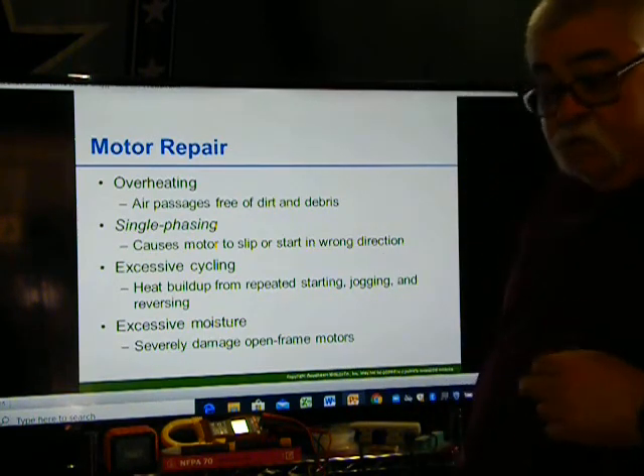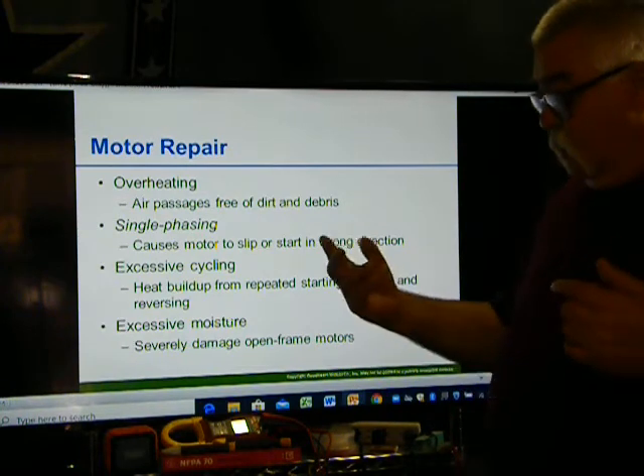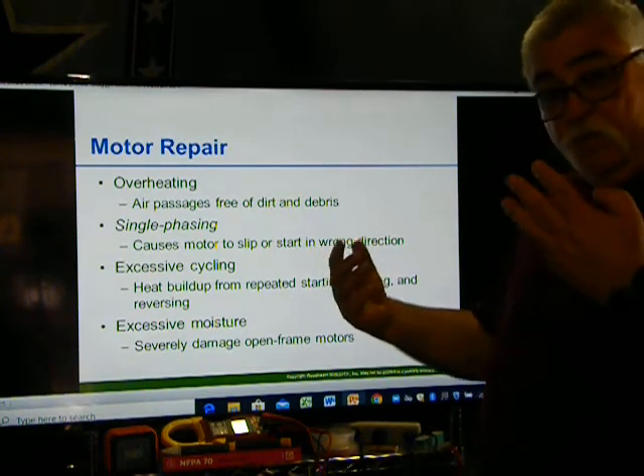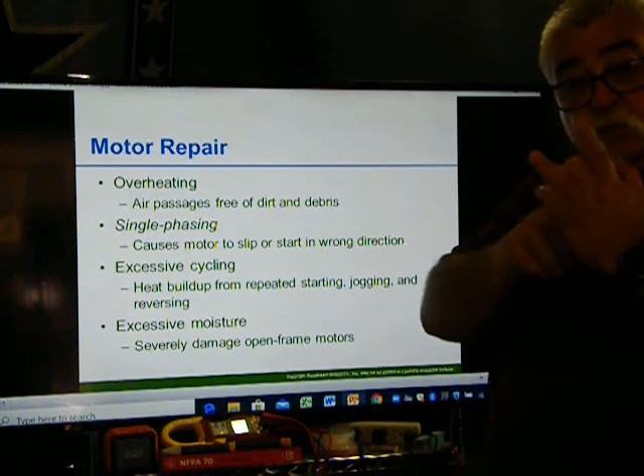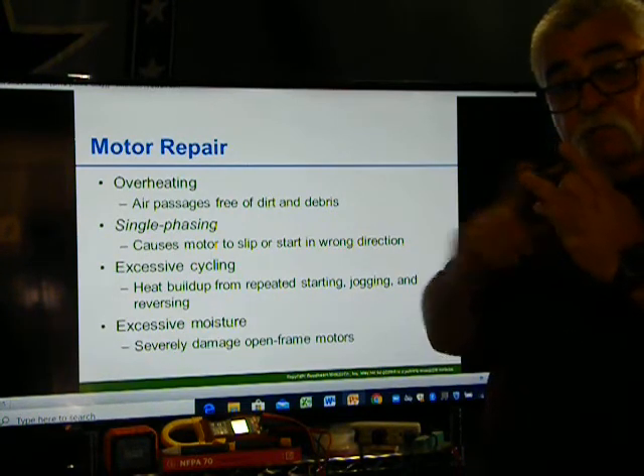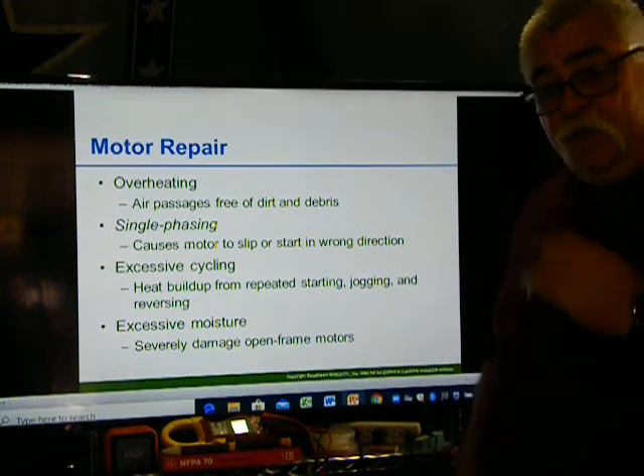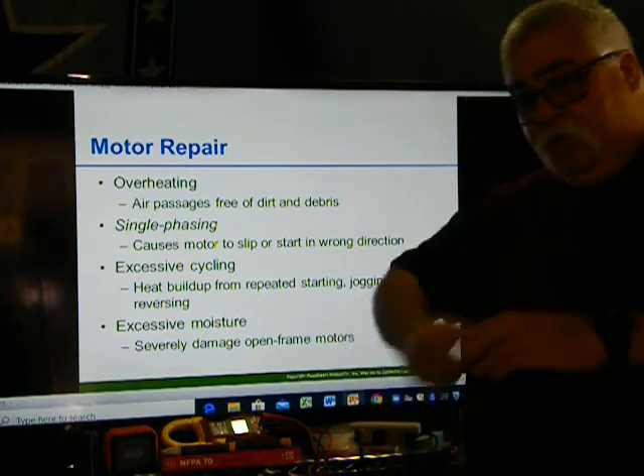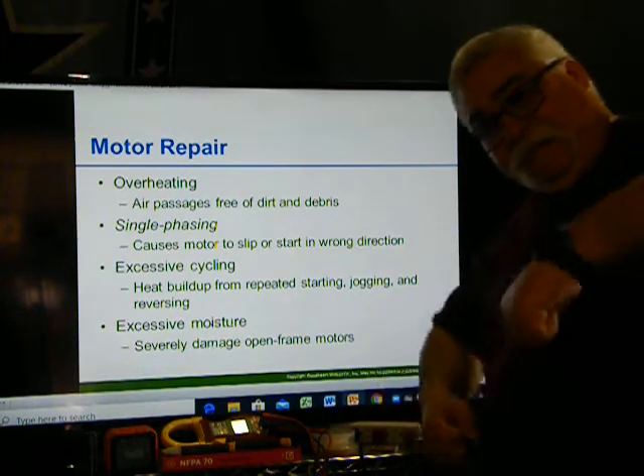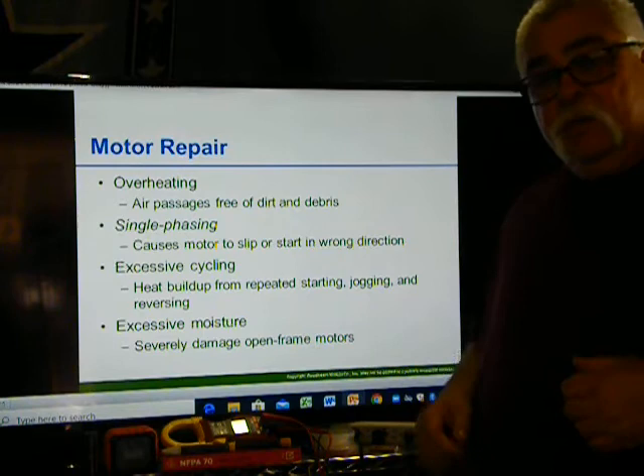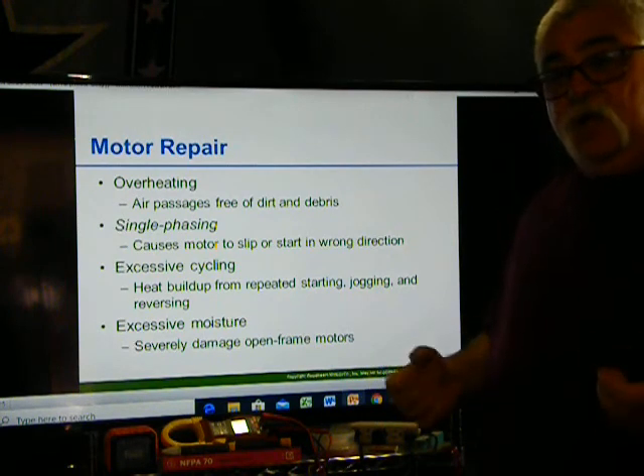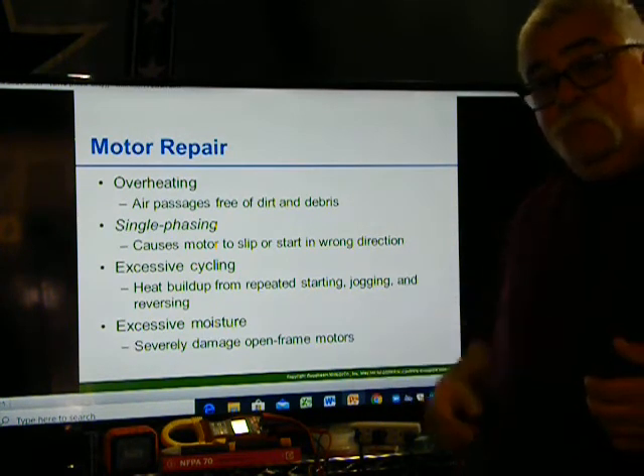So what is single phasing? Single phasing is when you have, let's say, 220 volts, and all of a sudden one of the phases drops out. But the motor's still trying to run. There's nothing there to make it turn, but it's just trying to. Guess what? The windings start to get hot. Why? Because it's not moving.